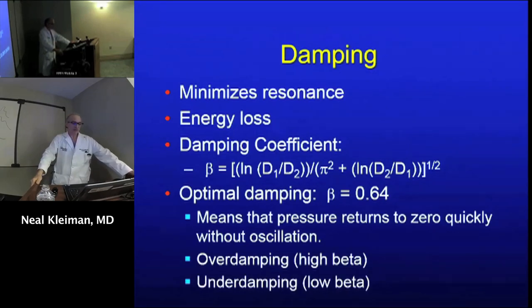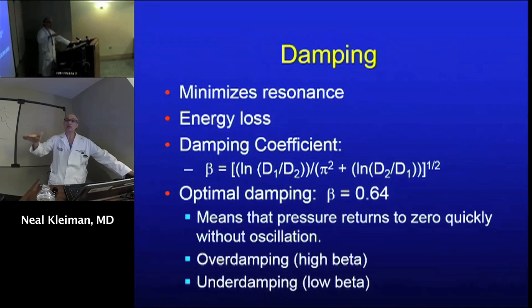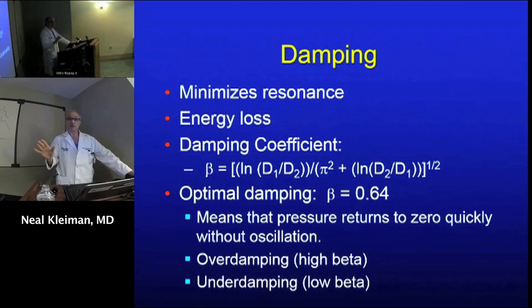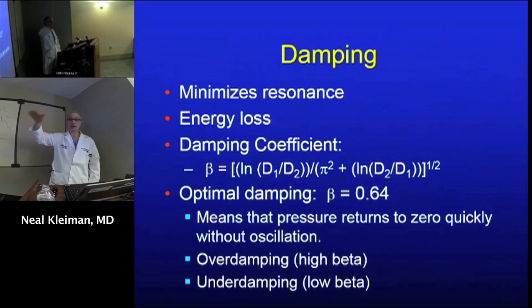A steel tube probably won't do it. What this means is that if you come close to the fundamental frequency of the transducer, it won't bounce like a spring, it returns to zero and then stops. We actually used to test for this, the biomedical guys did at one time. This was called a square wave test, and the square wave test was really simple. They'd take a 60 mil luer lock syringe, connect it to the transducer, pull, and then release. You'd measure the oscillations in the transducer and how long it took the pressure to return to zero. If it didn't return to zero very quickly, then it was time to discard the transducer.